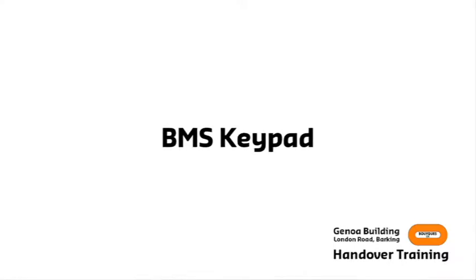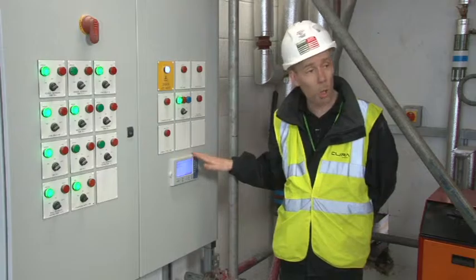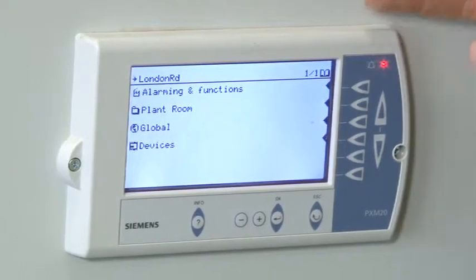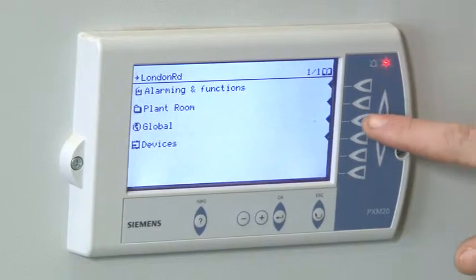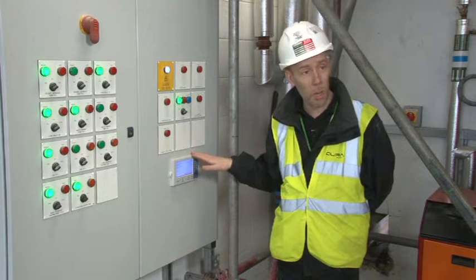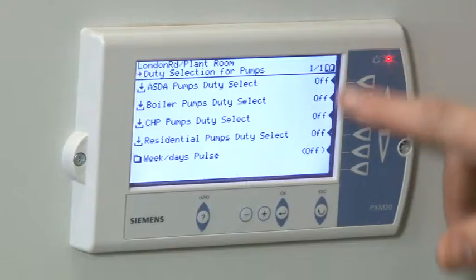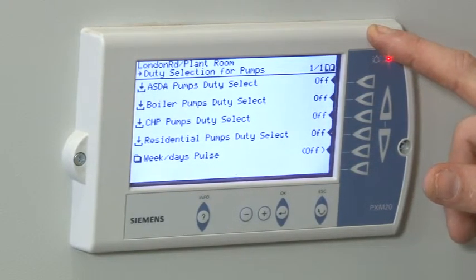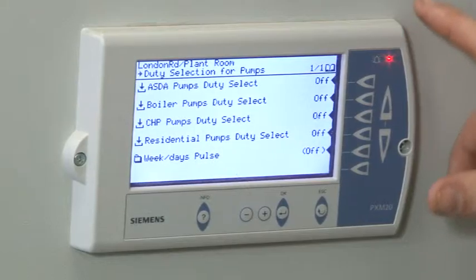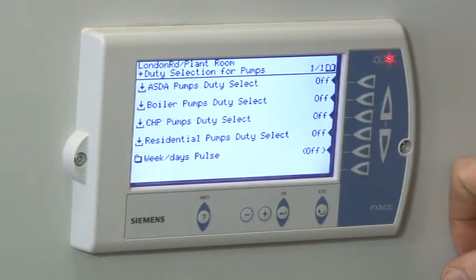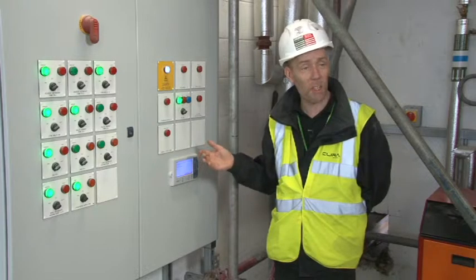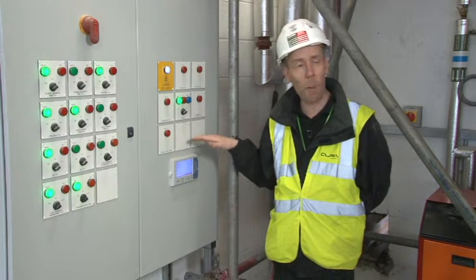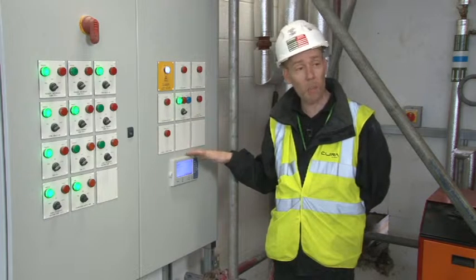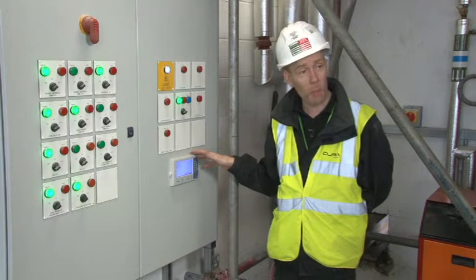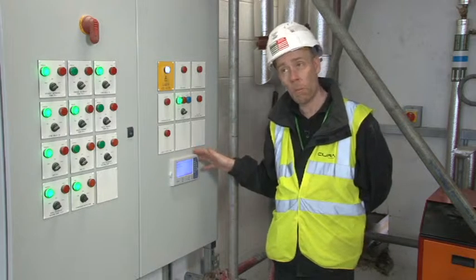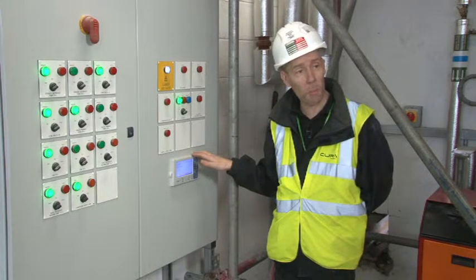For local engineering purposes, we have a localized keypad. It's password protected, so people can't mess with it. The password would be available within the O&M documentation. It's not something we normally issue to people unless there's a requirement for them to have the password, because there is the ability to switch plant off, change settings, or make the plant inefficient. So we prefer, basically, if you have a maintenance company, we can give them the password, they can then make adjustments that they feel are necessary for your building, and then obviously they can monitor the system from this point as well.